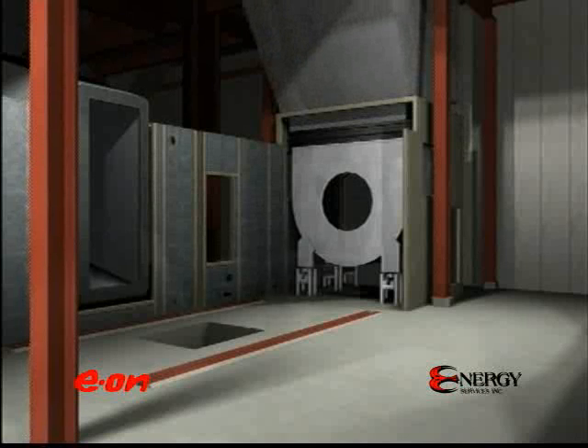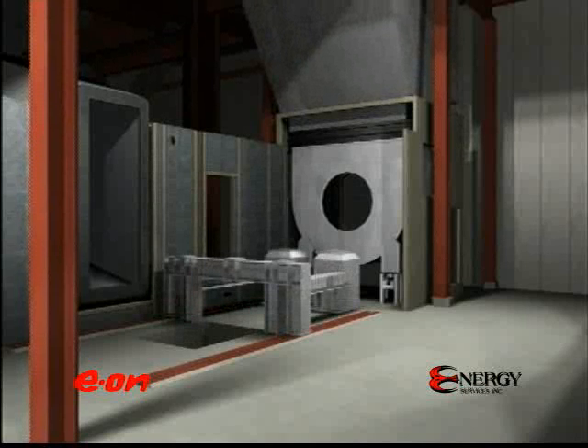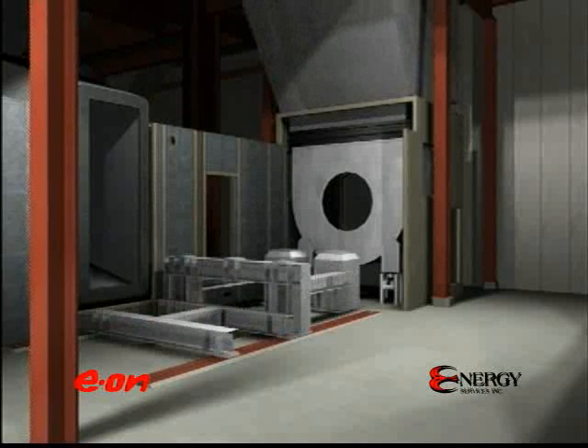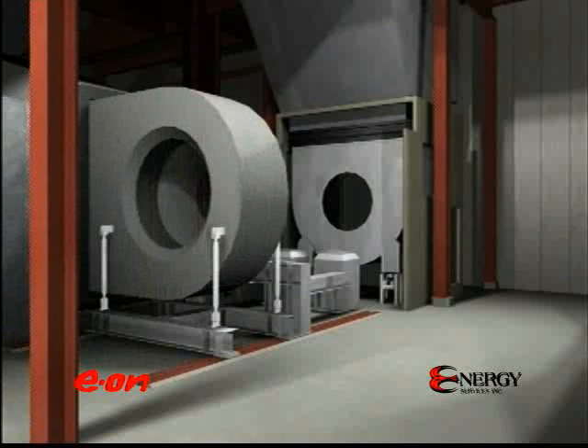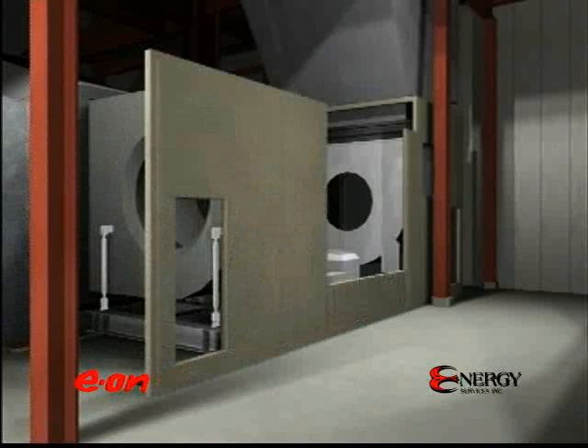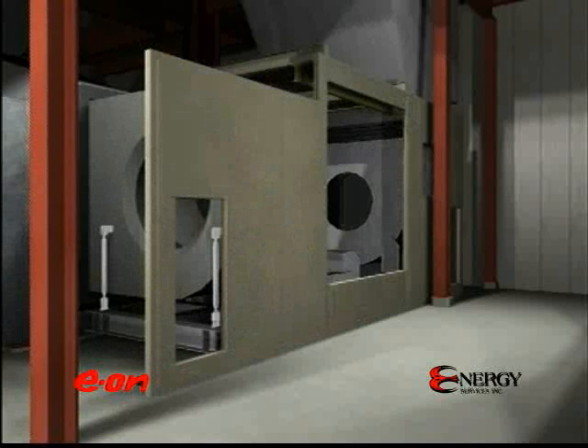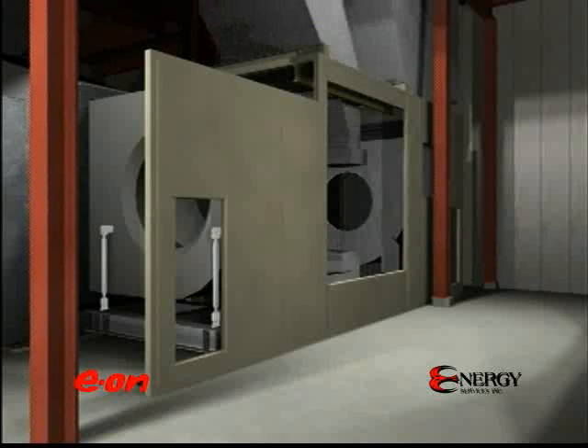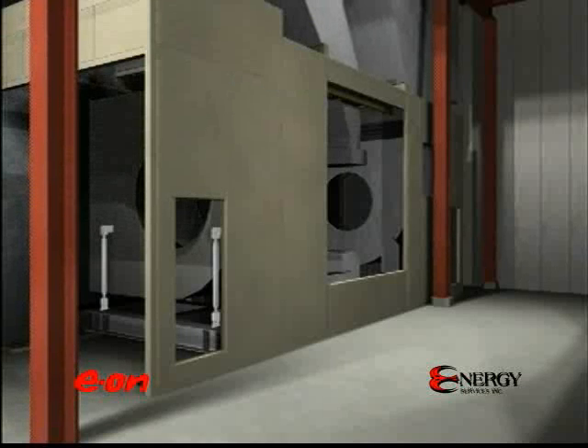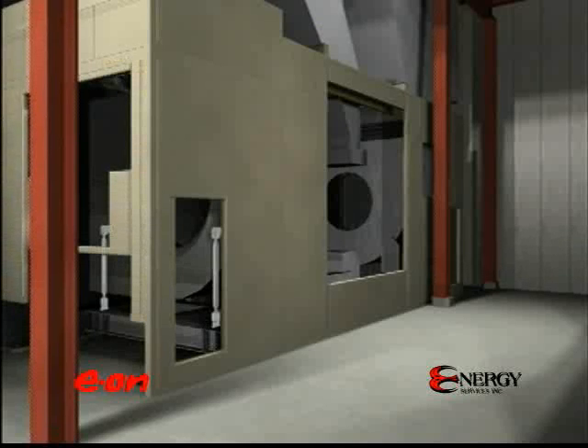Also, the radial inlet plenum, the gas turbine engine base, and the exhaust collector and its base were installed before the near walls were erected and bolted together. The central enclosure roof section was placed with the engine removal trolley already installed, and the VBV exhaust duct was installed from above. The final roof section was bolted in place, and the common wall that would separate the engine enclosure from the generator enclosure was fitted in place, completing the Unit 2 enclosure.